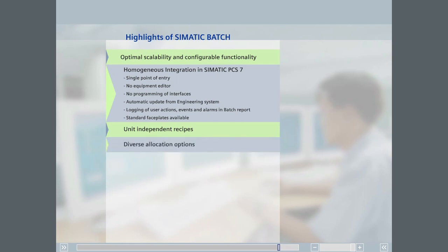SIMATIC Batch supports dynamic unit allocation; units can be allocated based on a variety of strategies. The batch planner can assign a specific unit to use during batch planning. SIMATIC Batch can dynamically allocate a unit based on the process classes assigned to the recipe unit procedure. The recipe author can allocate the unit at the beginning of the batch or when the unit is needed at run time.